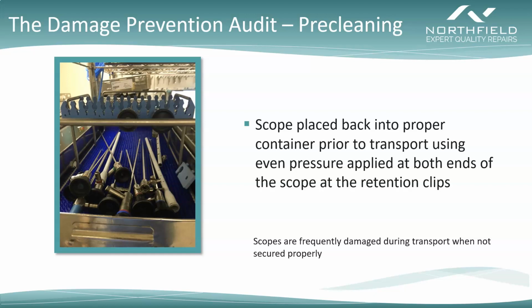Now, keep in mind also that if you are not using a container to transport your scopes back to decontam, that's a lot of damage that can occur during that phase. Your case carts, remember, don't have shocks on them, so every single bump in the floor, every single bump against the wall, all that shock damage gets transferred through that cart into the scope itself, and so a lot of damage can occur if you're not using those containers for your scopes during transport.